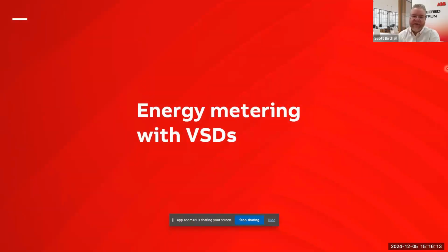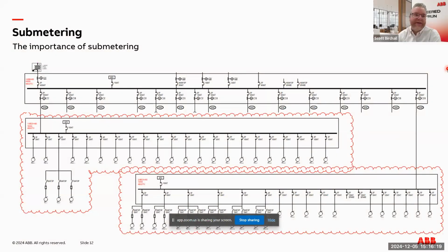So now I want to transition a little bit into some of the secrets that are in VSDs. There you go. I slipped up for the very first time, called it a VFD instead of a VSD, and talk about the metering capabilities of the drive. What you see right here is a partial one-line diagram. Don't worry, you don't have to read all this little fine font here. But what I want to do is, this is actually the building I'm in right now. So I got the main transformer here from the utility. Here's my main switchgear up top. And I blew everything away except for my mechanical room. So I have the mechanical room feeds off of this breaker here and off of this breaker here.